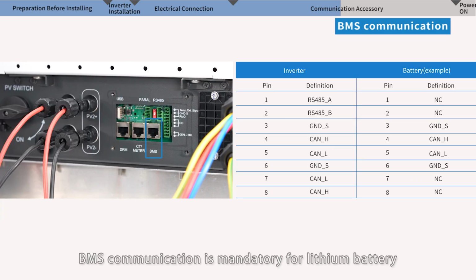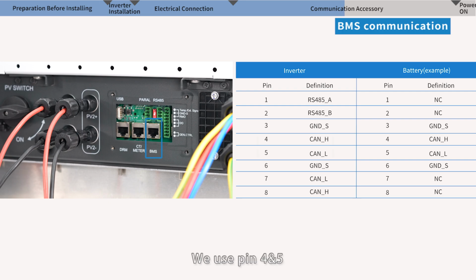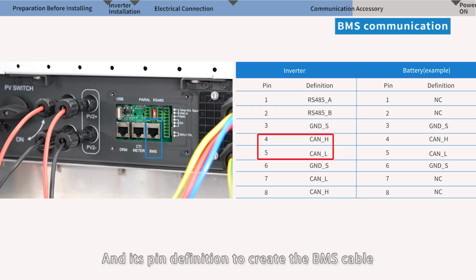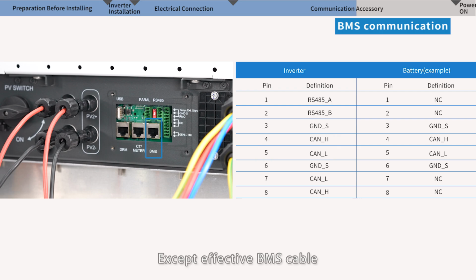BMS communication is mandatory for lithium batteries. On the inverter side, we use pin 4 and 5 as CAN-H and CAN-L. Please refer to the battery manual and its pin definition to create the BMS cable. Note: do not accept a defective BMS cable. Please also make sure the inverter and battery protocols match. The inverter will void its warranty if an unapproved battery is used.